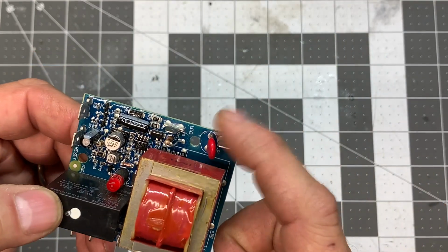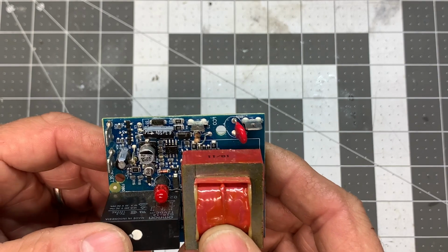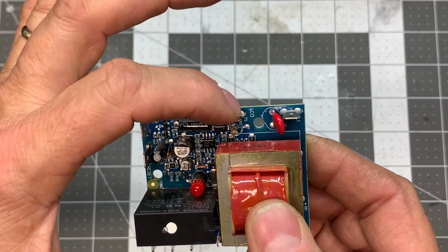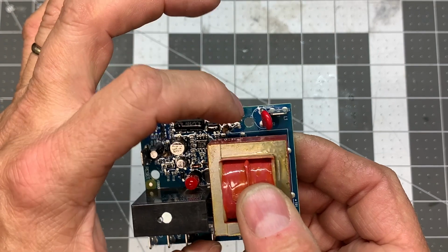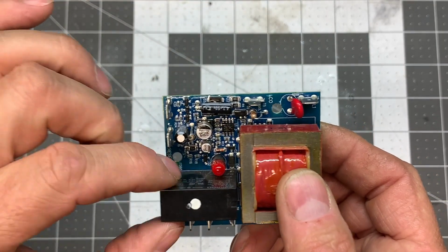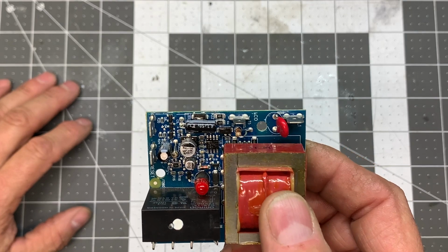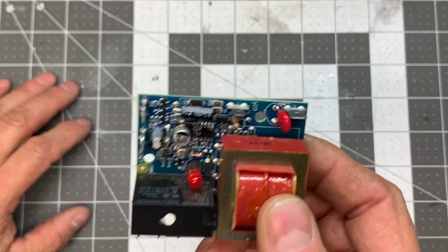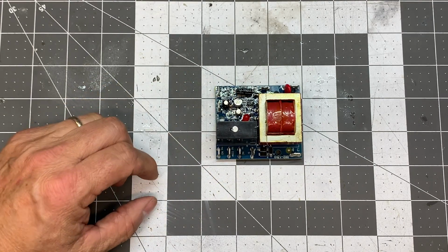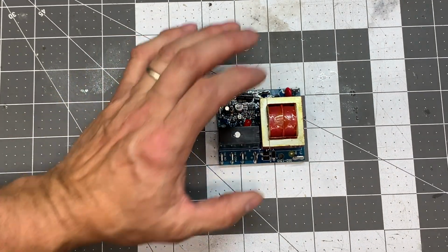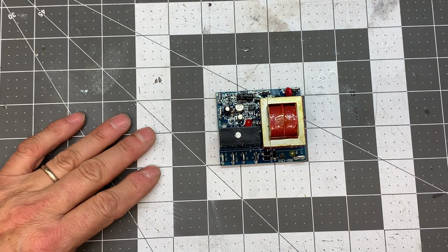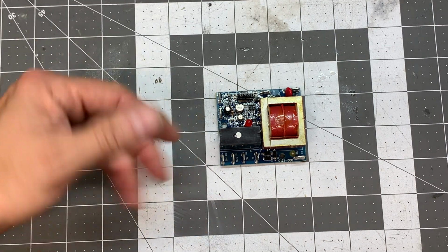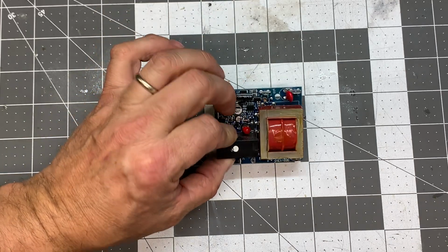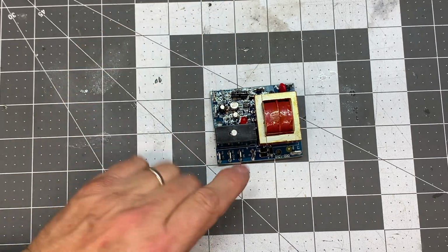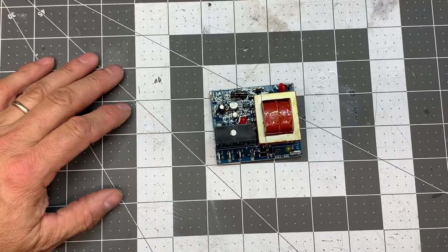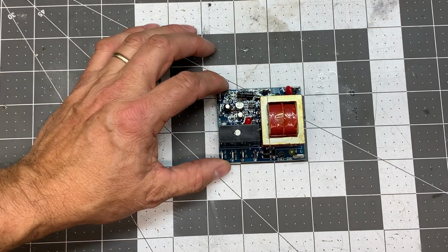I'm going to hook 120 volts up to the circuit here, and if we have the right resistance between the low water cutoff and the ground connection here, we should get a red light and the relay contact should close. And so we're going to see what happens there when we hook this up. Initially, this board would light up and work for a few minutes, and then after just a couple of minutes, it would go into fault. The light would go out or go dim. I'm not sure why that was happening. And the relay would drop out, and then it would throw the computer on the boiler into alarm.